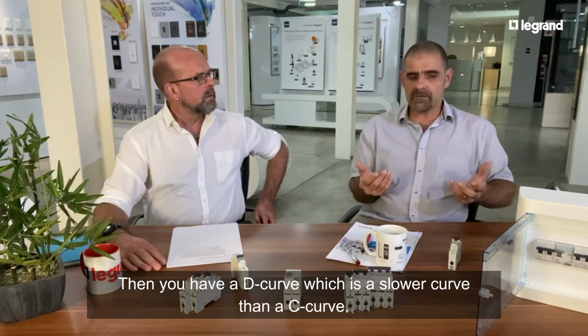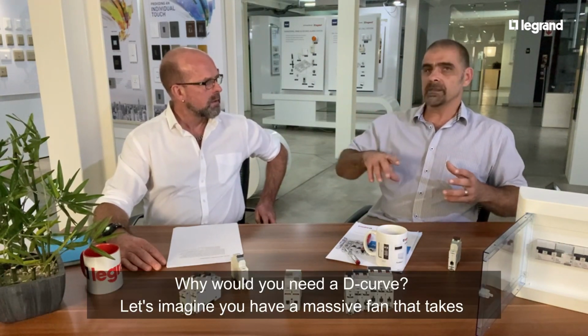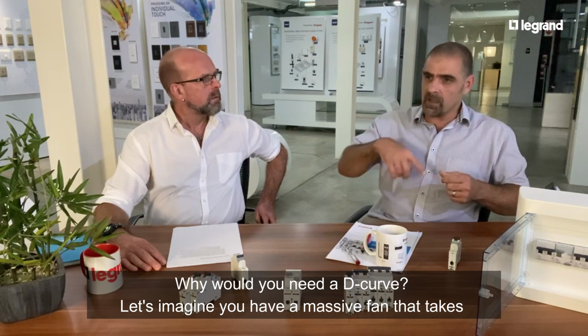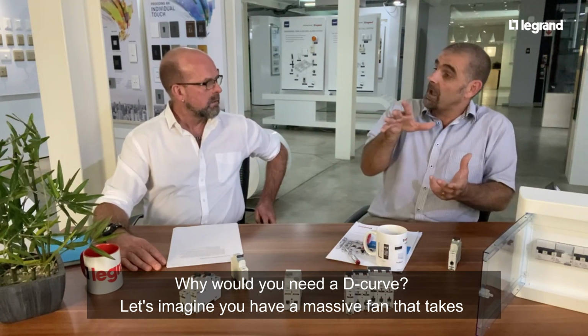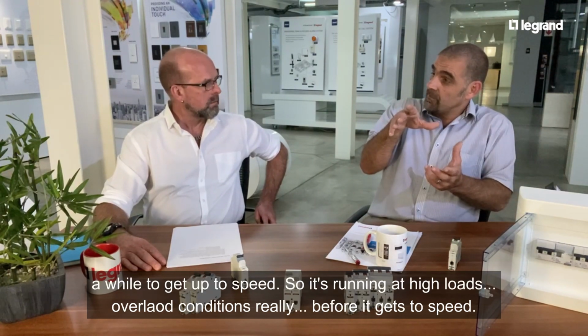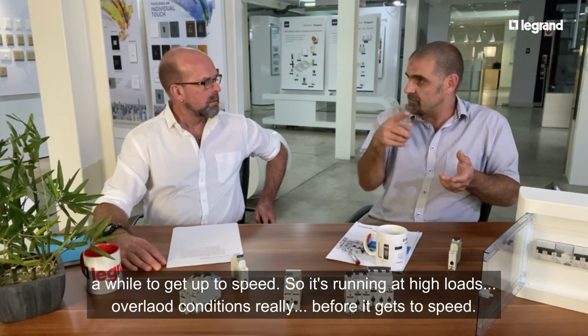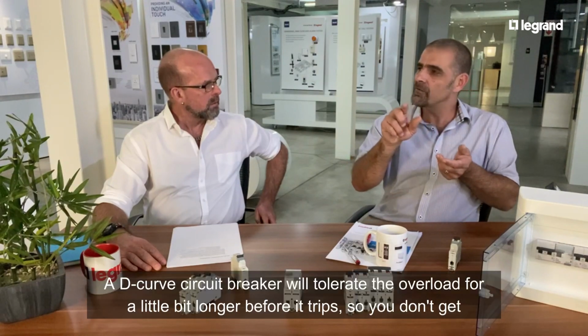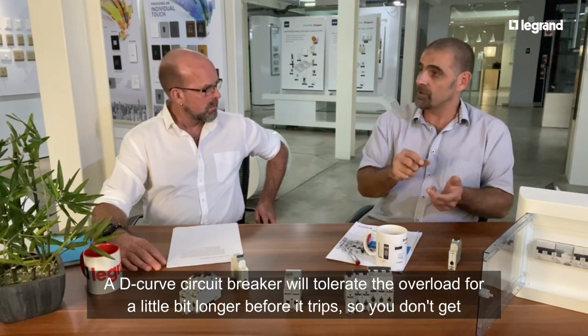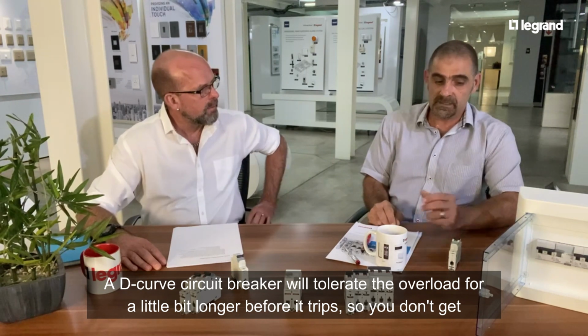Why would you need that, Sean? Imagine a big fan that starts up. This is a massive fan, and it takes a while to get up to speed. So it's running at high loads, in overload conditions really, before it gets to speed. That circuit breaker will tolerate the overload for a little bit longer before it trips, so you don't get nuisance trippings. So essentially that's what your B, D, and C curves are for.